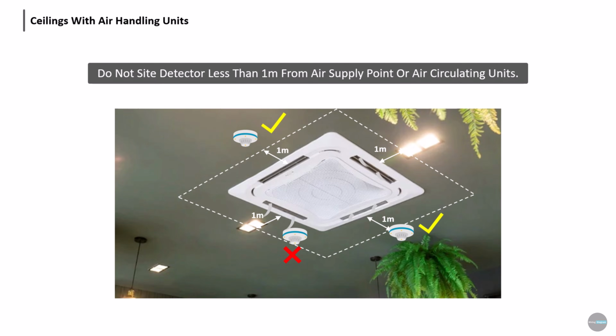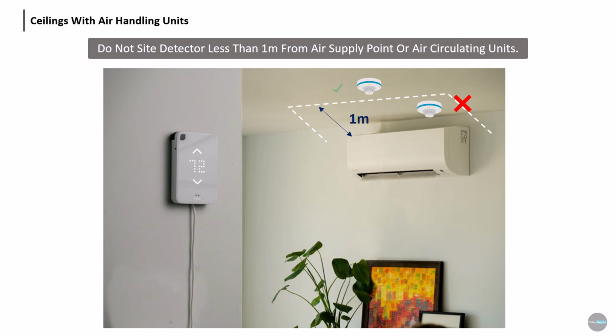If a room or hall has an AC unit, air handling unit, or air duct, let's see how to design the detector placement properly. The detector should be installed at least 1 meter away from the AC unit, air handling unit, or fan. This is because these units create airflow, and during a fire, the smoke or heat may get carried away by this airflow, preventing it from reaching the detector. Sometimes, people make the mistake of installing the detector too close to the fan or air handling unit, but this is not the correct method of installation.